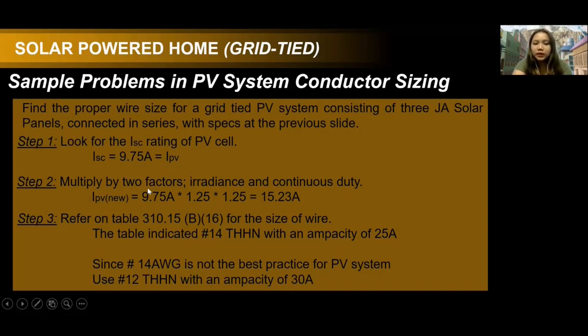Step 2, multiply by 2 factors: irradiance and continuous duty. Yung ISC natin, ita-times natin sa irradiance kasi init ng araw, tapos yung continuous duty, yung pag ginagamit natin nang tuloy-tuloy. 25% parehas, 25% sa irradiance, 25% sa continuous duty. So ti-times natin siya sa dalawang 1.25. 9.75 amperes times 1.25 times 1.25, 15.23 amperes na yung new ampacity natin.